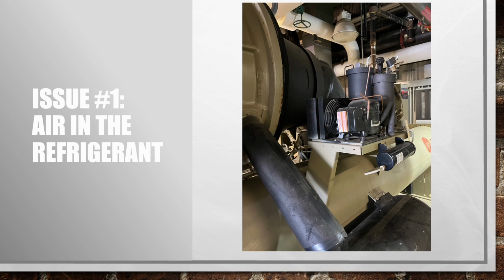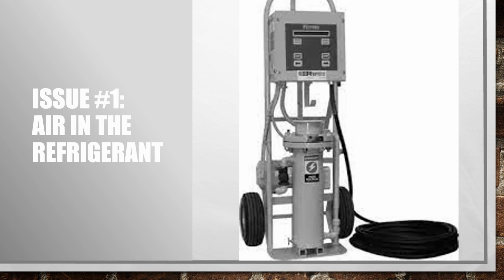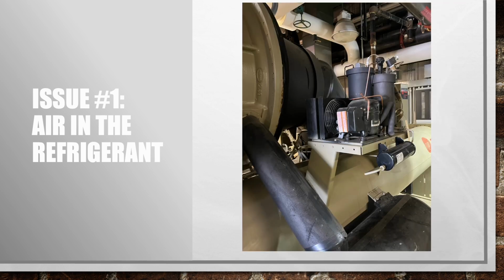So you'll more than likely need to leak check this, and to do that you're going to need to pressurize the system and then leak check it. Like I said before, it may be worth looking into the purge system as well. So if you do have leaks in the system and it seems like they're not very substantial, if they're really small leaks, then you're going to need to look into seeing what's going on with the purge unit as well. You're pretty much always going to have some leaks just because the system's in a vacuum all the time.